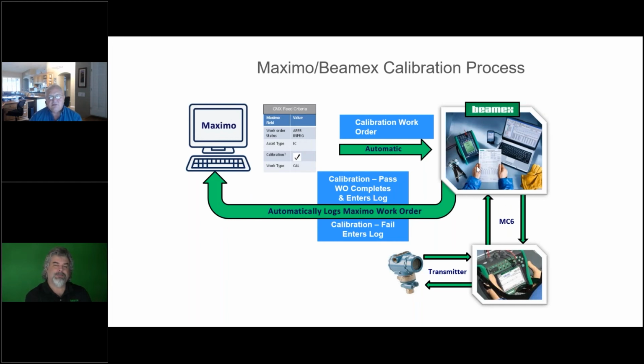Beamex is our system of record for the calibration. If we want to know what the calibration was, we go to Beamex, because it's an actual calibration — nobody can argue that point. But Maximo is the asset system of record. So if you want to know that it was generated, it was calibrated, everything's got the name on it, it's got the date on it, then Maximo is your record to go to.